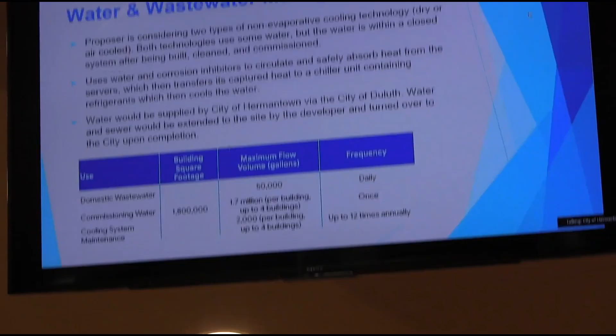You mentioned something added into the cooling water—what is that? We're working with the wastewater receiving facility to determine exactly what chemicals we'll use in the closed loop system. It depends on a few factors, but generally they'll be anti-corrosive and antimicrobial agents. We're working with WLSSD now to determine that; they'll dictate how much and what we're allowed to discharge. If we're not allowed to discharge to them, we'll ensure that material, whether from maintenance or commissioning, is collected and shipped to a facility that can handle it.